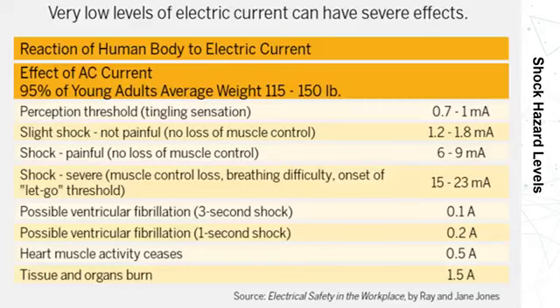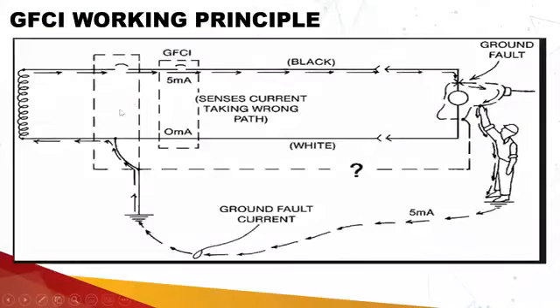So that means if there is a current difference, then the current is not following its path and it is getting shorted through a different part. For example, here if we see the GFCI working principle, the current is 5 milliampere, for example, going and returning back to the system, or 10 ampere this device is using, and the 10 ampere is feeding back.